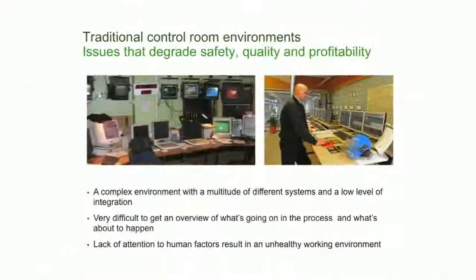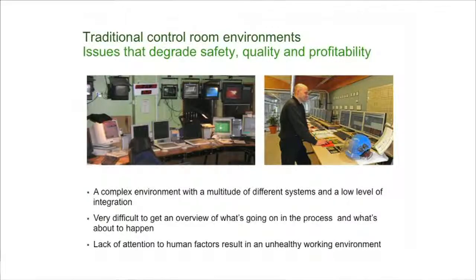You can see, I like this picture. It's quite a few monitors of different types, and as you can see, not two of them are the same. And no one bothered to make them look the same in any way. They are different size, resolution, colors, positions. So that's completely uncoordinated. That doesn't help the operator. And way too many keyboards. I have better pictures like that. But you also see it on the other side.